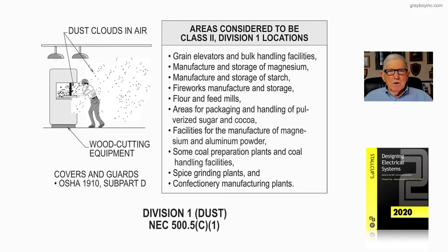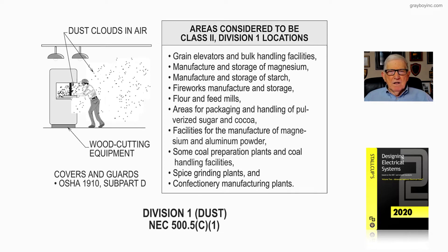Now let's look at Figure 21-3. It deals with Class 2 Division 1 locations, and it gives a laundry list in the boxed-in information of what is considered a Class 2 Division 1 type location. You can see grain elevators and bulk handling facilities as bullet one, and if you drop down to the bottom bullet, you have manufacturing plants and things of that nature — the different locations classified as Class 2 Division 1.